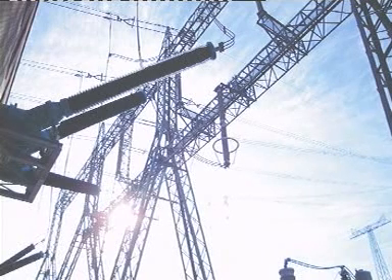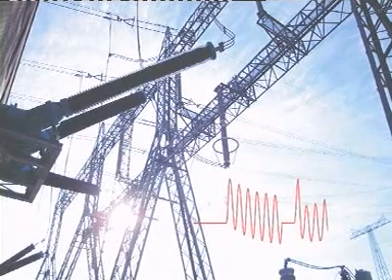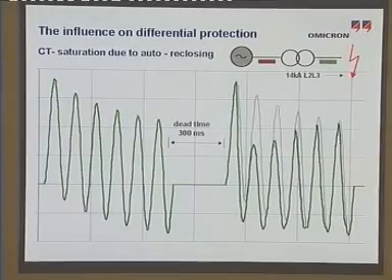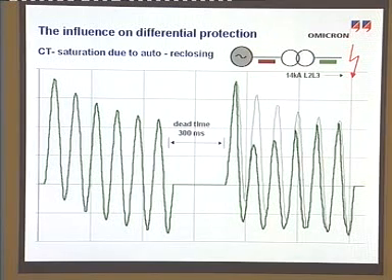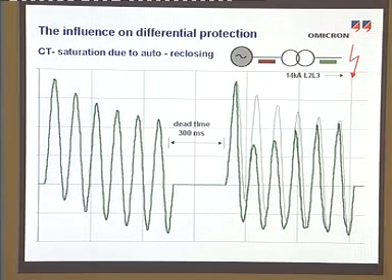Remanence — the ability to store magnetic energy — plays a role not to be neglected, especially with regard to auto-reclosing. As shown in the figure, a short circuit current of 14 kA with the first fault does not lead to CT saturation. With the unsuccessful re-closure, the CT is saturated due to remanence.